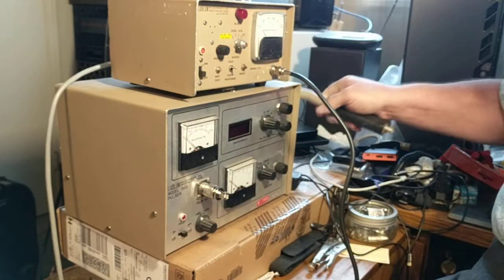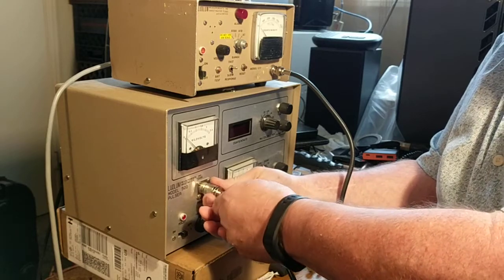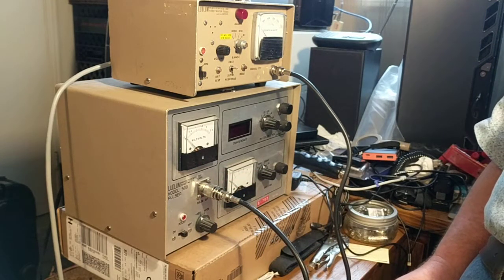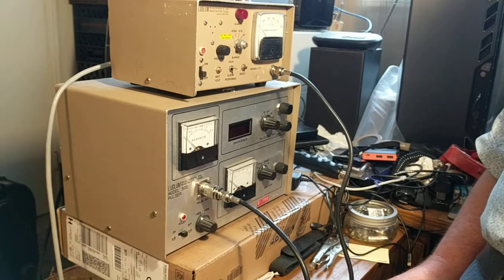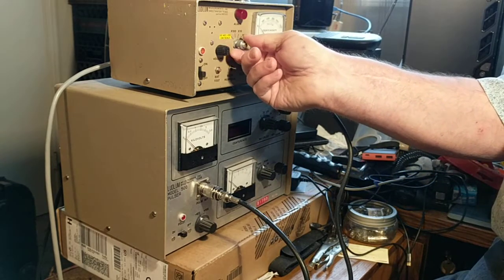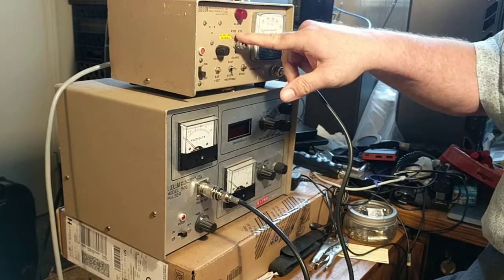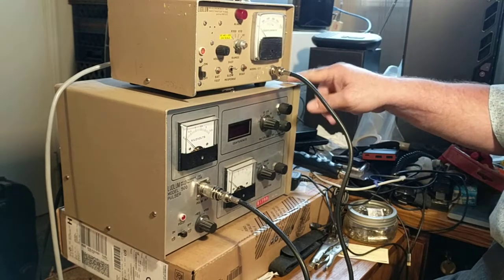In order to calibrate this unit you need to use a Ludlum Model 500 Pulser or equivalent. There are three steps to calibrating it. First, make sure the high voltage is set correctly. Second, make sure the calibration or discriminator is set correctly. Third, make sure that for each of the ranges — times 1, times 10, times 100 — the appropriate counts match what the Pulser generates. The Pulser generates the counts; this generates the voltage.